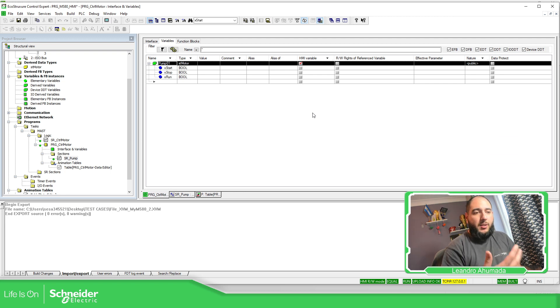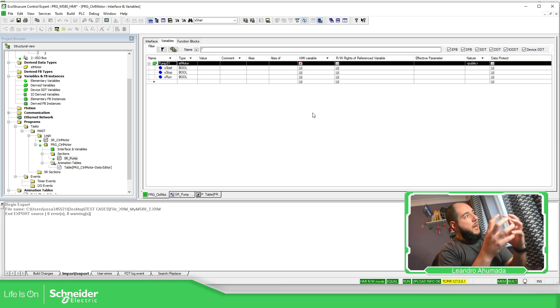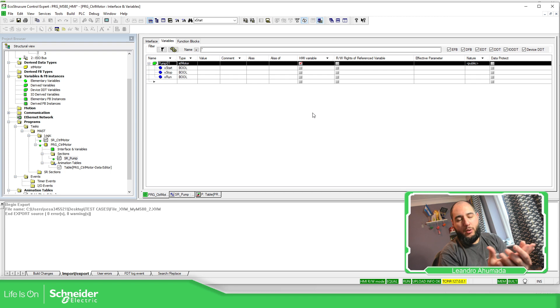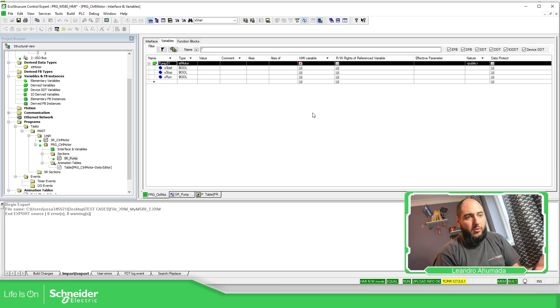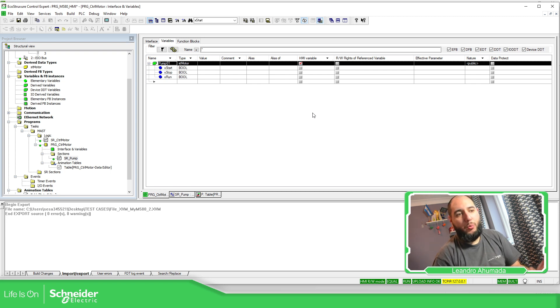So if we need this to work — imagine this program unit is your code in a box — these interface variables are the inputs and outputs. But even if you use public or private, it doesn't generate any addresses or unlocated variable addresses that allow the PLC to communicate with the HMI. So what we need to do is associate the interface with something that has an address. This is how I will work around it.